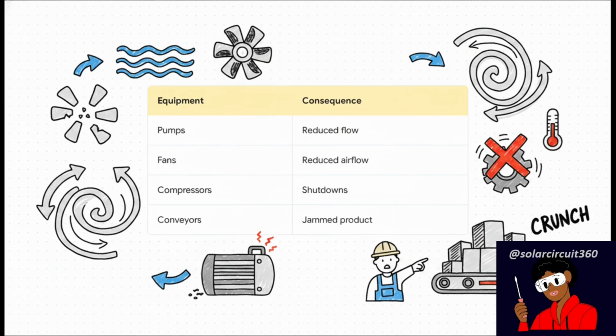And worse, the motor's own internal cooling fan runs backward, which leads to dangerous overheating. Compressors? They are even less forgiving. Running a compressor backward can cause an immediate shutdown, trip internal protection limits, or even cause catastrophic permanent mechanical damage in a matter of seconds.